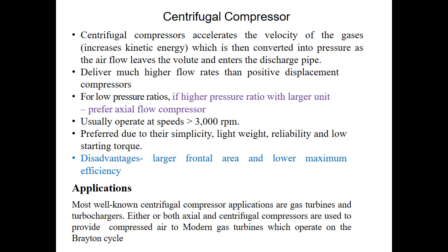Now we will focus on centrifugal compressors. The centrifugal compressor is a radial flow dynamic action type compressor. It utilizes mechanical energy imparted to the machine from an external source to increase the static pressure head of air. It consists essentially of a stationary casing containing a rotating impeller which imparts high velocity to the air, and a number of fixed diverging passages in which the air is decelerated with a consequent rise in the static pressure. The diverging passages are known as the diffuser.